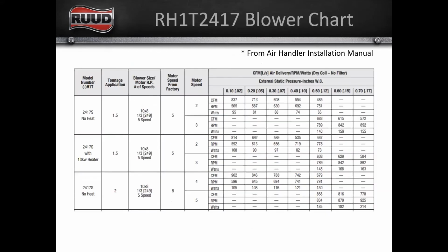On this one, we're going to look at a little bit different table. This is from an RH1T, and the air handler that we're using is an RH1T 2417. We have a half inch of static. A couple of things I want to point out about not just this air handler, but every piece of indoor equipment that we have: it has a speed set from the factory. So this air handler, this 2417, this is pretty common. We ship on high speed, right? So every one of these ships on 5. We don't know what the right tap is for your application. We don't have any idea. So we had to pick something. We pick high speed. They all ship on 5.